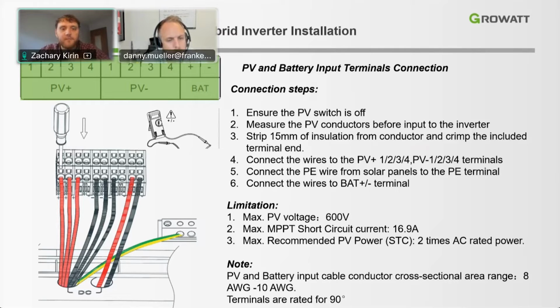So the limitations for this: the max PV array voltage is 600 volts. This is very important. This aligns well with the residential codes that are in place right now, and it is not recommended to go anything higher than 600 volts, as that could damage the system. Also, currently the maximum power point tracking short circuit current is 16.9 amps. So this will be raised in the future, but for the time being, according to our data sheet, it is 16.9 amps for short circuit current for each maximum power point tracker.